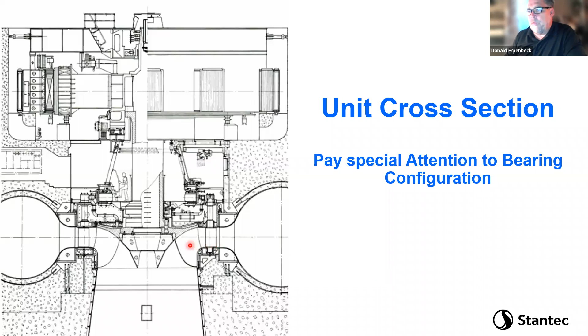Right, so this is a cross section through the turbine that failed. Here you see the runner that I said weighed 160 tons. Here you see the person. These always help in the picture. The shaft is actually hollow on the inside, so there's a set of stairs inside the shaft. The 730 megawatts of torque is obviously a big enough load that they rolled the shaft out of plate or forged it out of a ring, which some of the larger machines like Three Gorges are made this way.